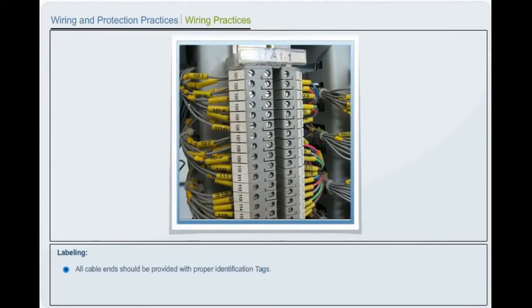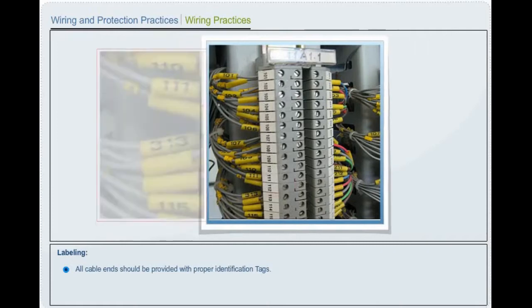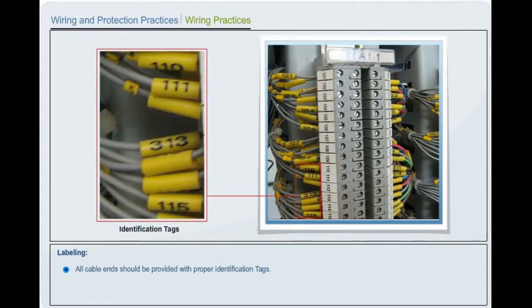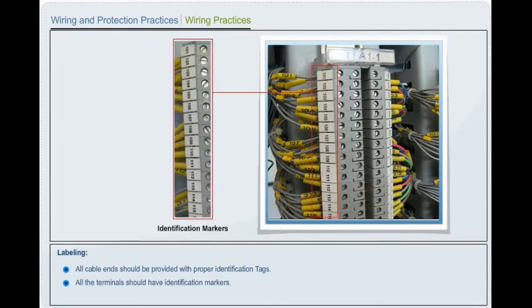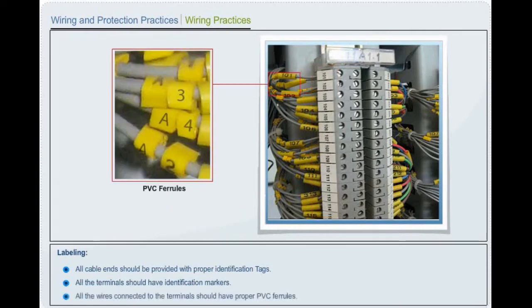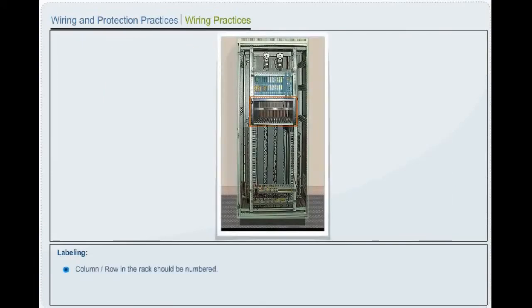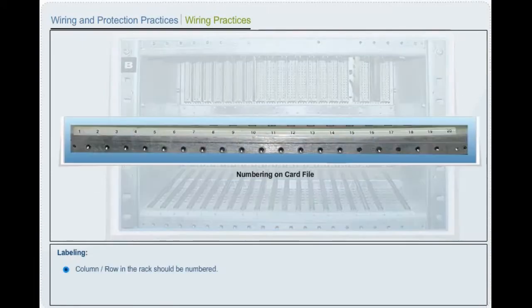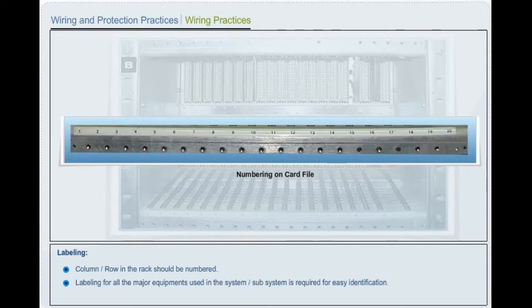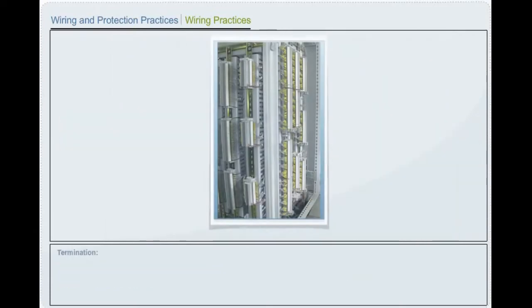Labeling. All cable ends should be provided with proper identification tags. All the terminals should have identification markers. All the wires connected to the terminals should have proper PVC ferrules. Column or row in the rack should be numbered. Labeling for all the major equipments used in the system or subsystem is required for easy identification.